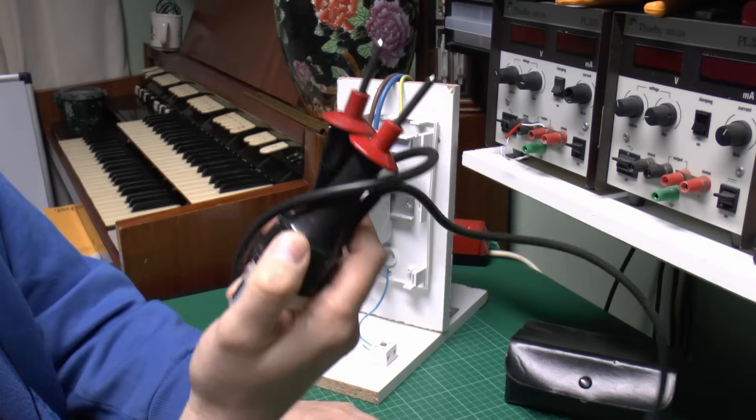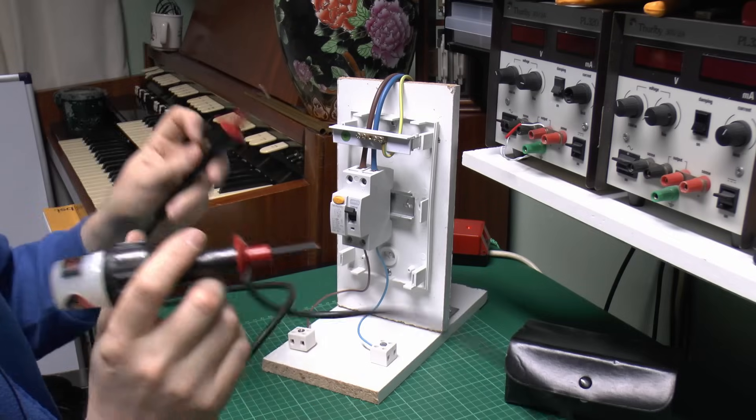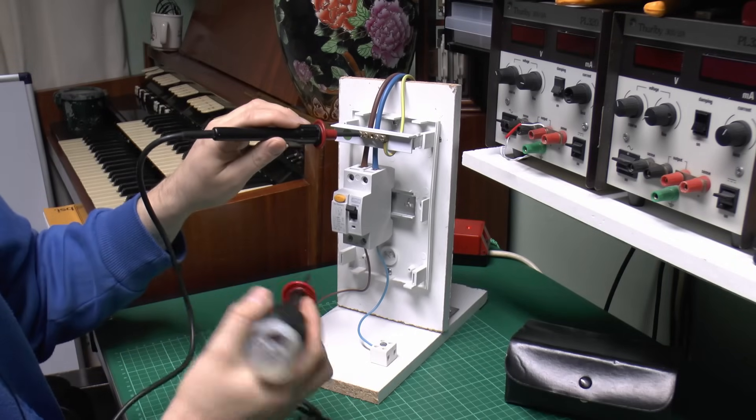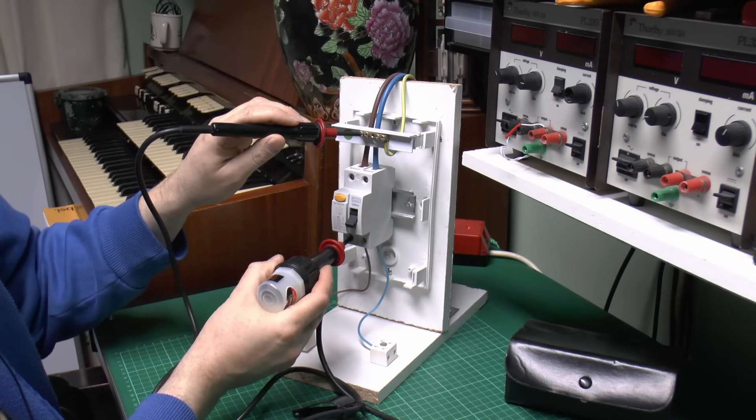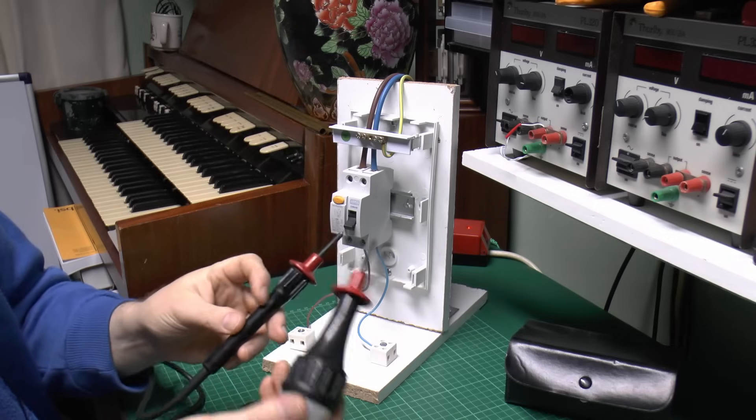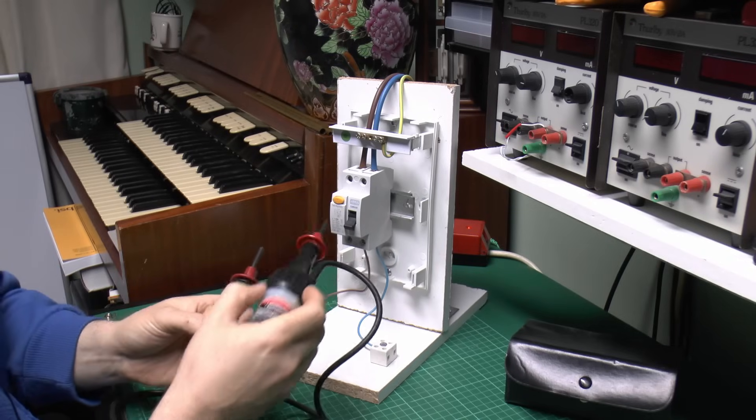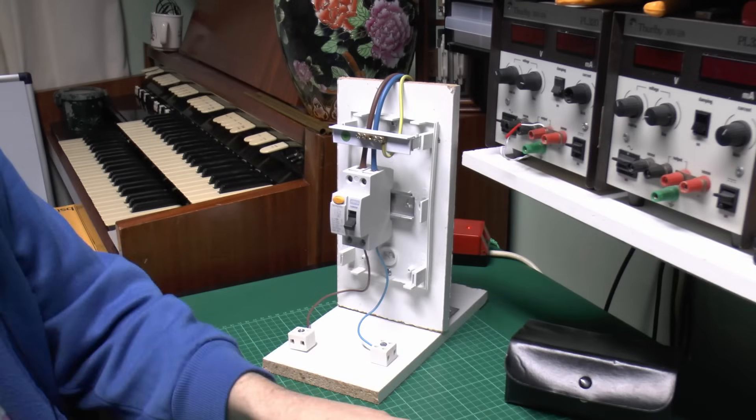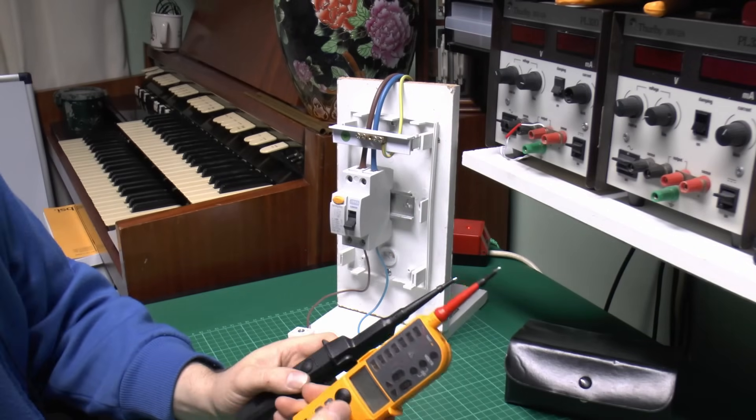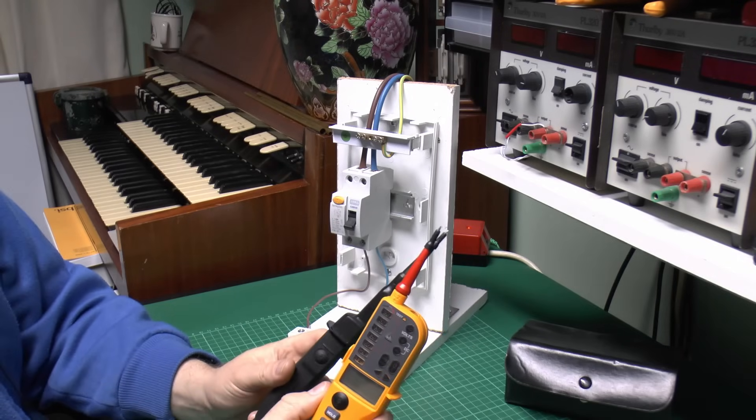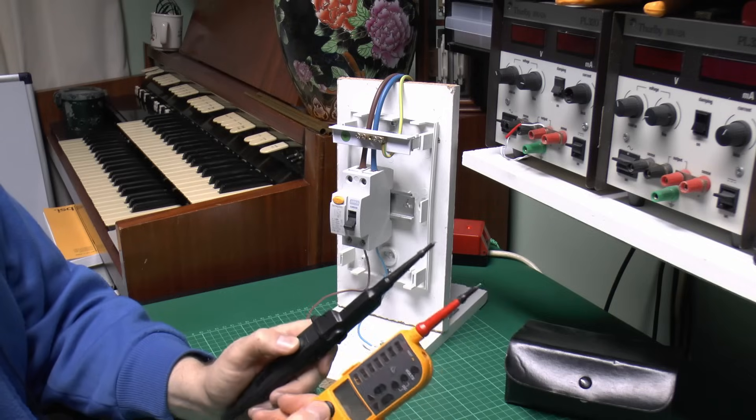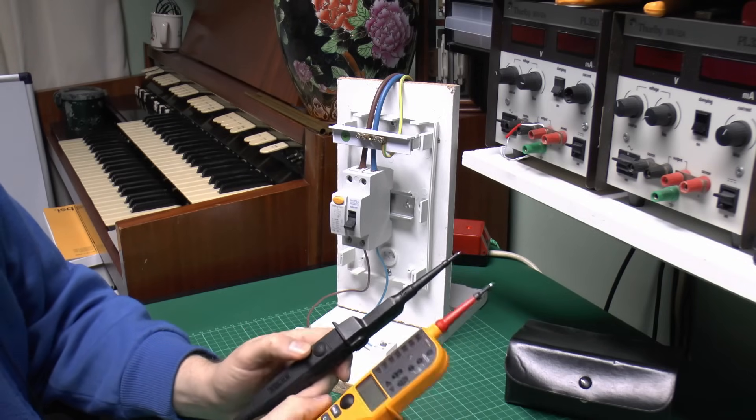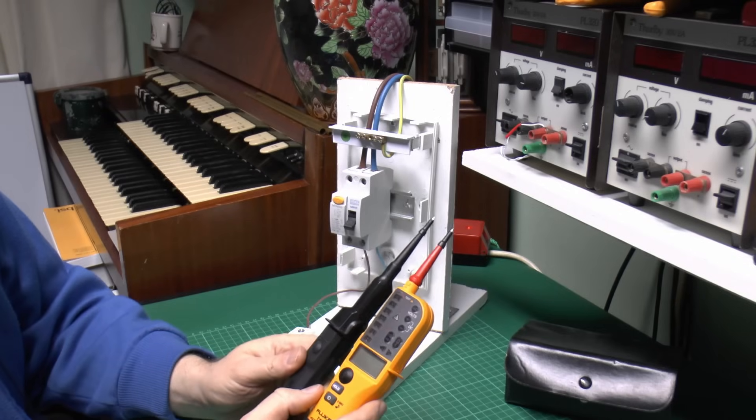Now one difference between these and the type with just the lamp inside is if you've got an RCD like this you can actually test from say the earth up here to the outgoing side of the RCD, and it will display the voltage just as we'd expect. But if you try to do the same thing with this one, then this is what actually happens. So again we'll just go from the earth terminal there and we'll go in the bottom, and let's see the RCD trips straight away, and that's simply because the current that this thing draws is far in excess of the 30 milliamps that the RCD requires to trip. This particular one on the other hand, being electronic, only draws a small current and hence does not actually trip the RCD.